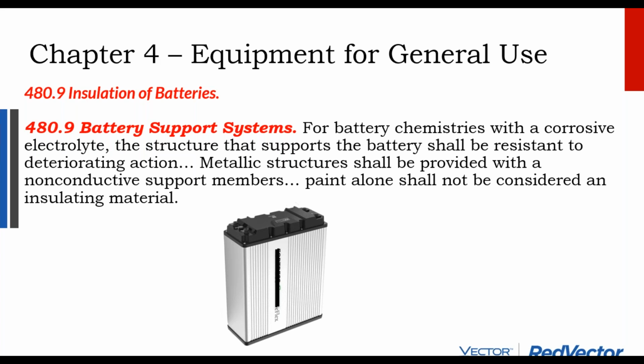Here is a battery that is designed for floor mounting, and it has an insulative, hard plastic base so that it can be set right onto that concrete slab. Similarly, you would put a rubber mat on your metal battery rack, or maybe anodized metal is more resistant. So painting the metal rack alone is not considered an insulated battery rack.